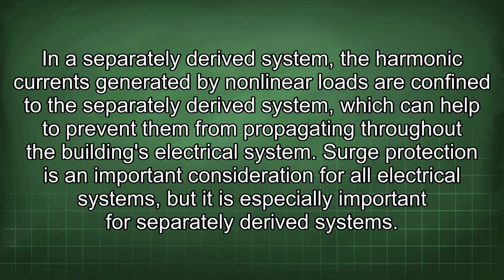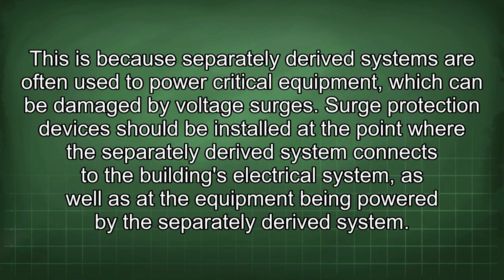Surge protection is an important consideration for all electrical systems, but it is especially important for separately derived systems. This is because separately derived systems are often used to power critical equipment, which can be damaged by voltage surges. Surge protection devices should be installed at the point where the separately derived system connects to the building's electrical system, as well as at the equipment being powered by the separately derived system.